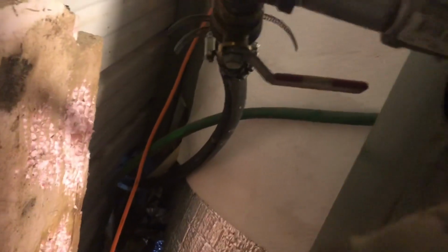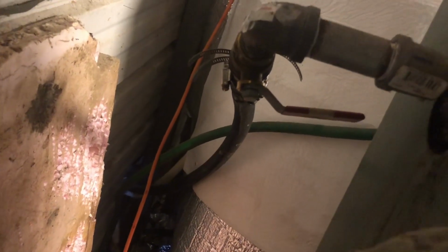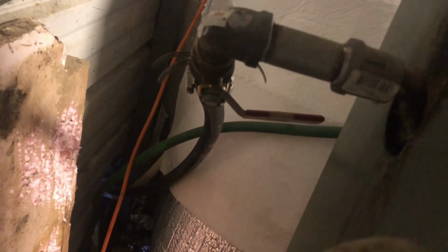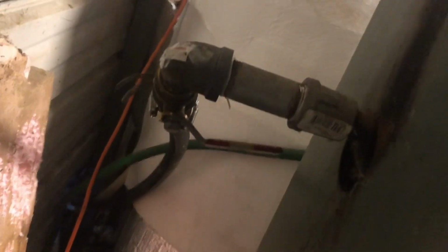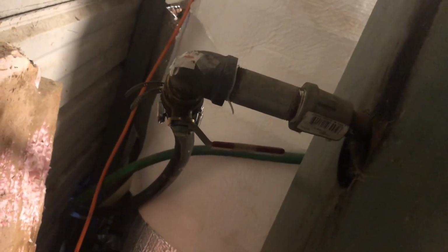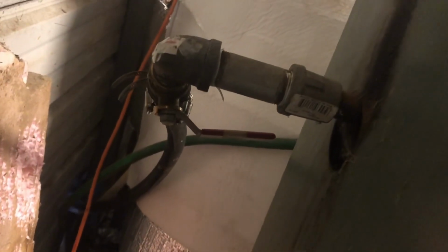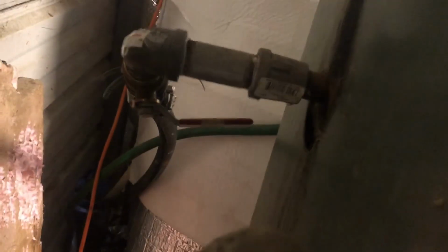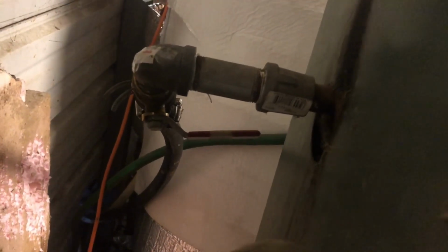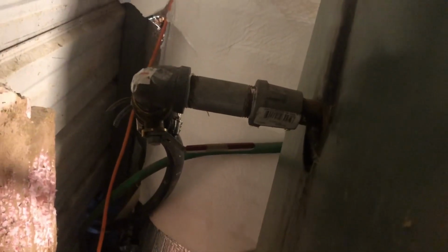Now what I had a leak with was this valve right here, my water inlet valve. This is coming from my water lines - I buried it along with the water that I'm circulating through the house and back to the boiler. This line runs through all that piping too, which keeps it from freezing. Once it comes up through here, all I have to do is turn that on to allow water into the system. That's just so I can fill the system back up without doing it by hand.